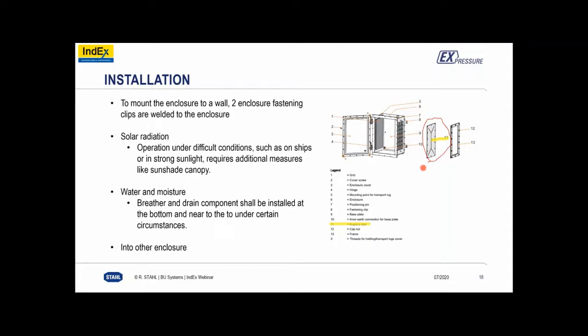However anybody wants to understand it, it's what opens up to release the pressure. So where you have the mesh here, where I have highlighted, that's obviously where the explosive pressure comes out. The rupture disc opens up, and the frame obviously holds that all together to the side of the EXD enclosure. So the EXS components are the mesh, the rupture disc, and that frame. That's how it differentiates from a typical EXD enclosure.